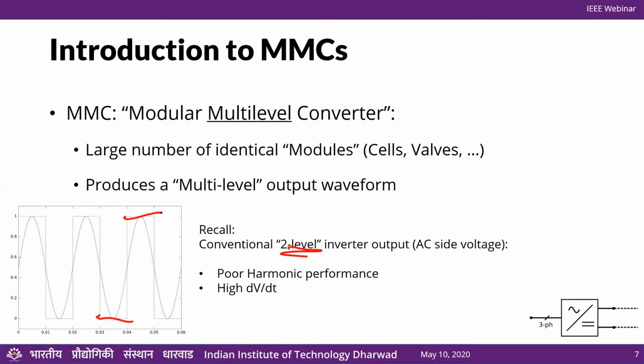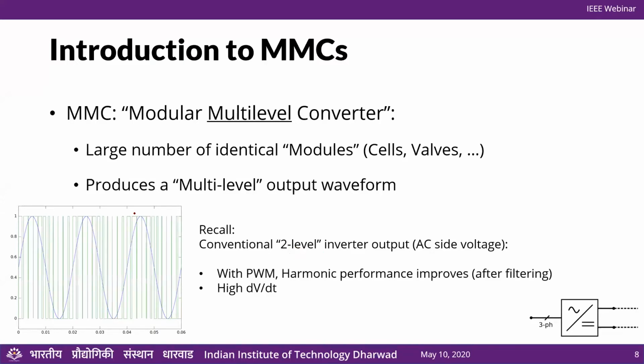So the voltage goes from 0 or off to full value very quickly, and that is very detrimental for a lot of reasons, which I won't go into right now. Imagine doing that when your DC link is hundreds of kilovolts, which is common with medium voltage drives or HVDC applications. In those cases, dV by dt is completely unacceptable.